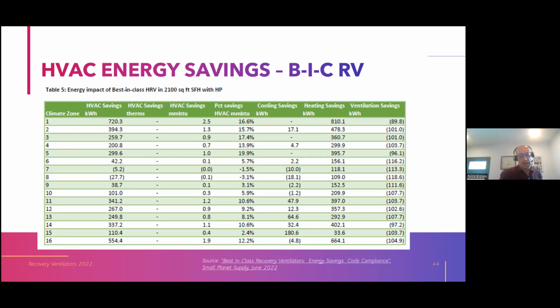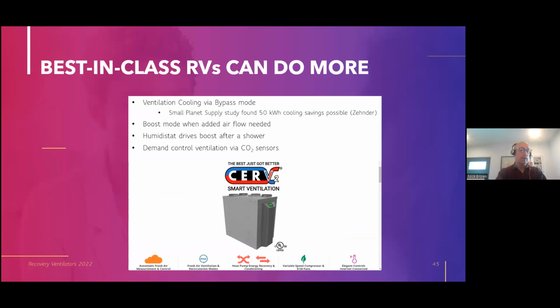But some of those best in class ones, I'm trying not to talk too much about particular brands, but Zehnder in particular has accessories for the distribution of the air that look like they really make the process simpler. I had to design my duct systems myself and buy the sheet metal duct and the flex duct, and I had a HERS-Rater friend do the duct design for me. So there are added benefits that you get for that cost. You also get some functions for that cost, and probably fault indication display as part of that bargain too, which, as I'm going to show you in the next section, boosts compliance credit.